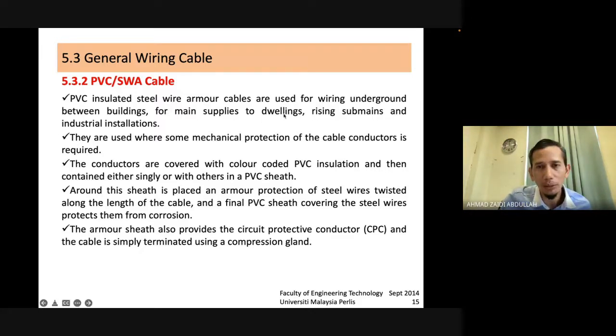From main supply to dwelling, rising submain and industrial installation, so this is related to your project. They are used where some mechanical protection of the cable is required. Definitely, because we need mechanical protection since we install underground and we care about the workers. Maybe they use a hoe to dig the soil to plant vegetables or something, so the armour takes the mechanical force instead of the cable, so it is safe.